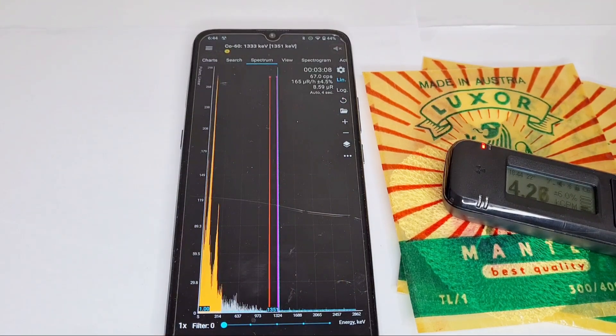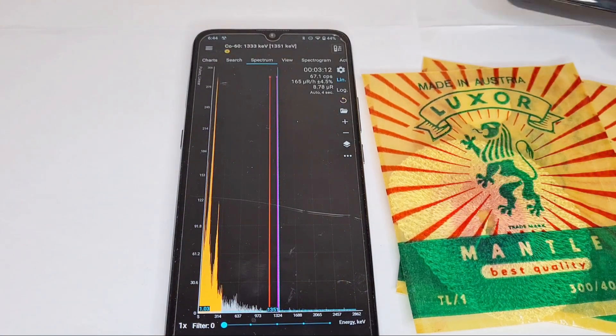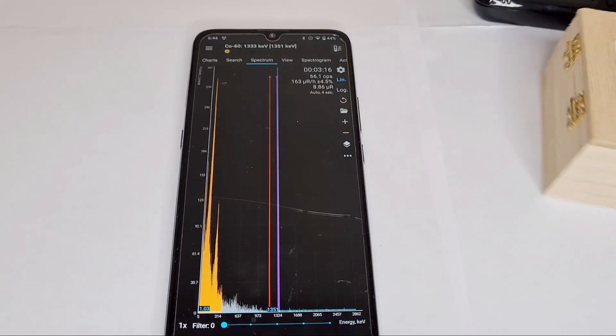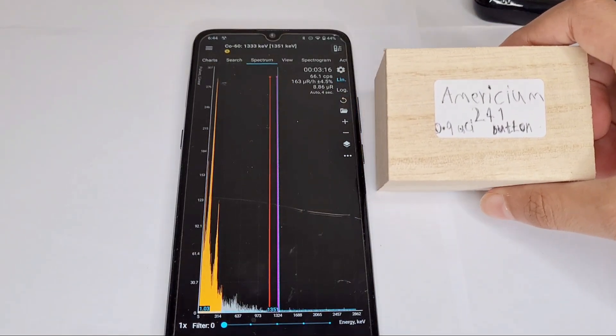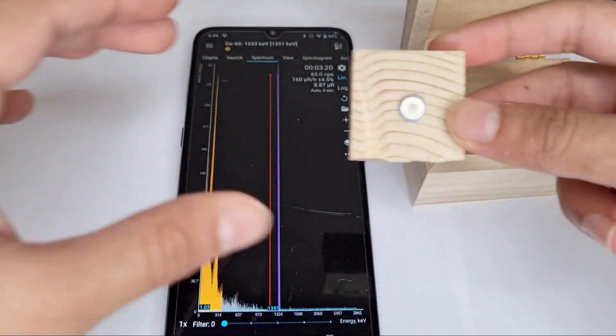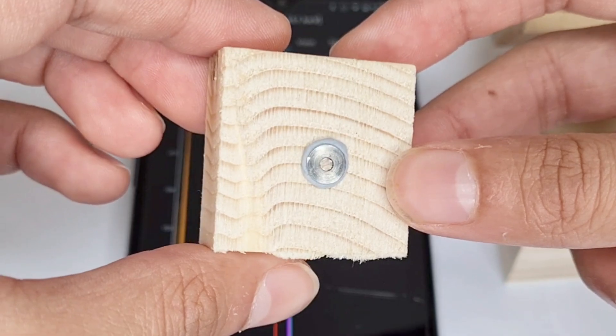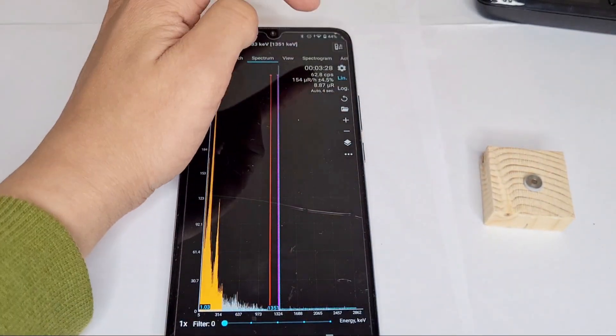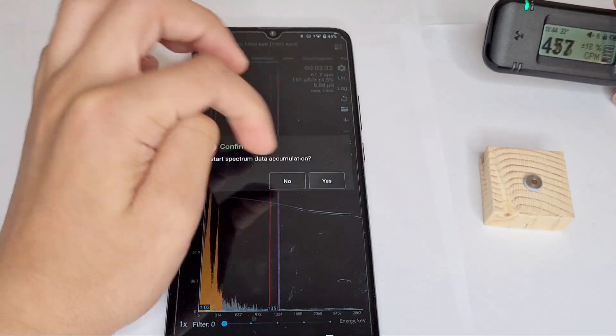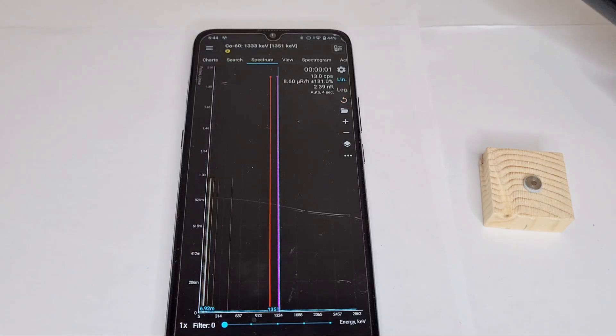Now here's the alarm going off again. Let's try something else, something a little bit more spicy. Here I have Americium-241, 0.9 microcuries on a button. So here it is. I'm going to put this down and then here I'm going to press restart accumulation.